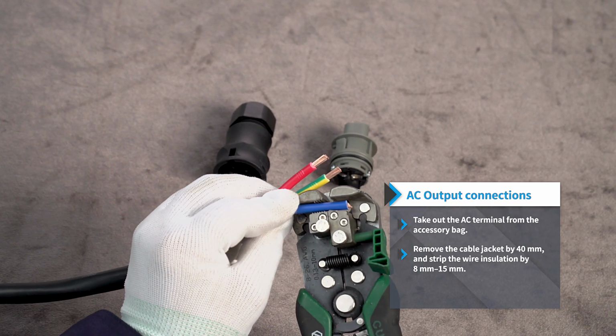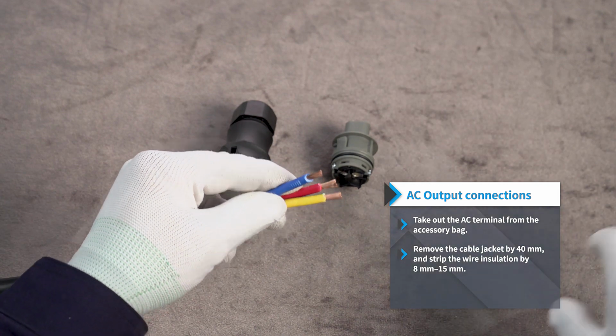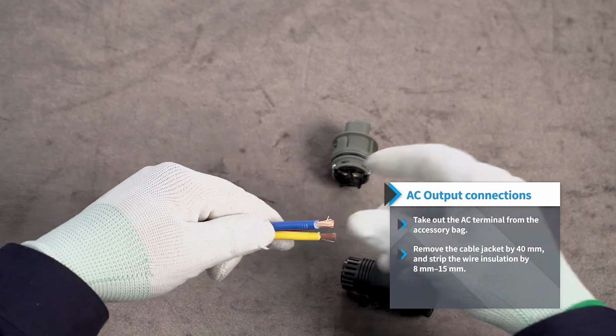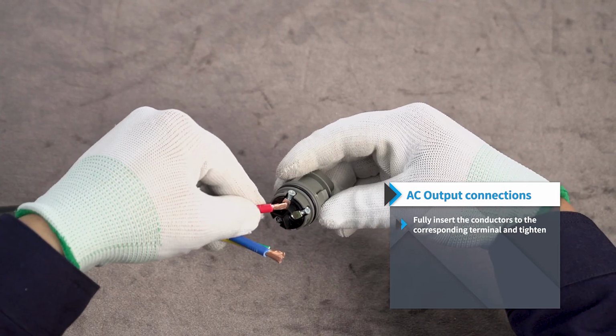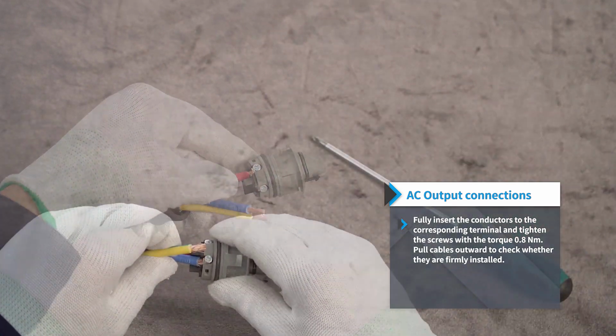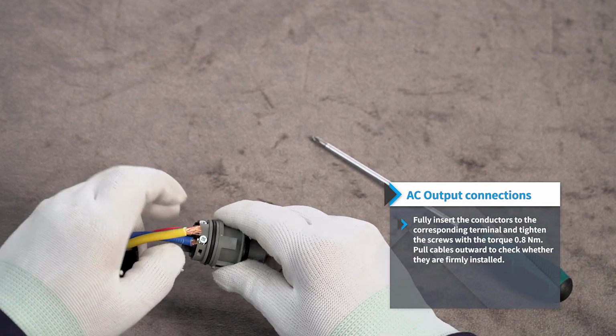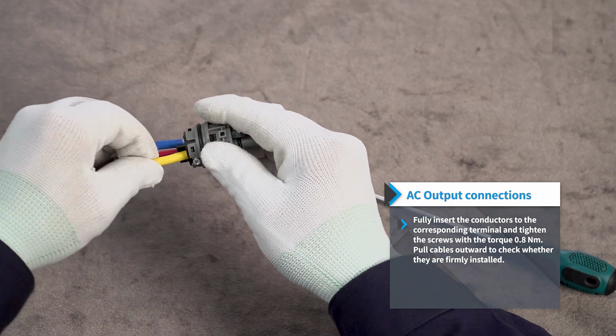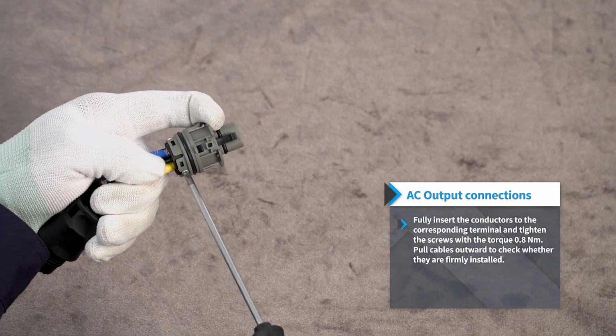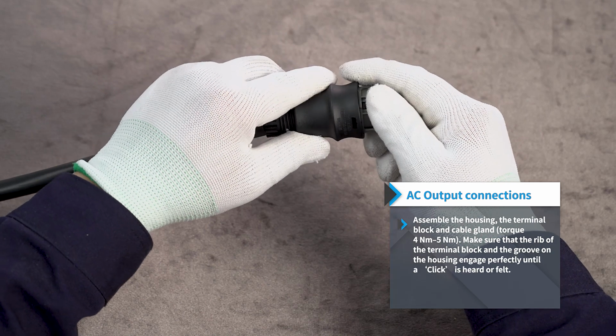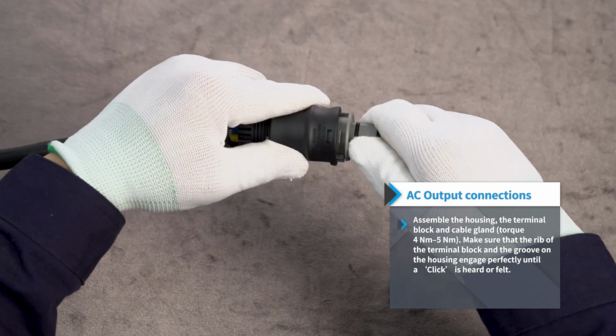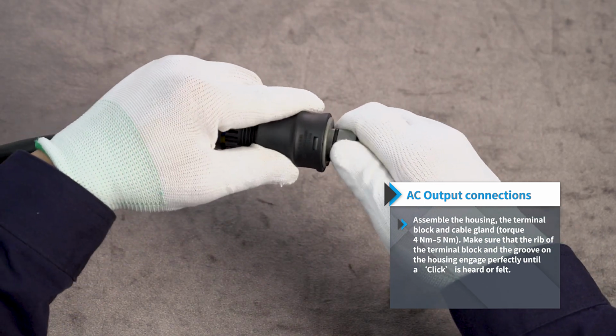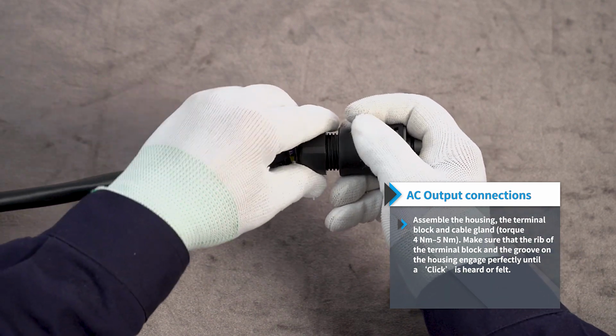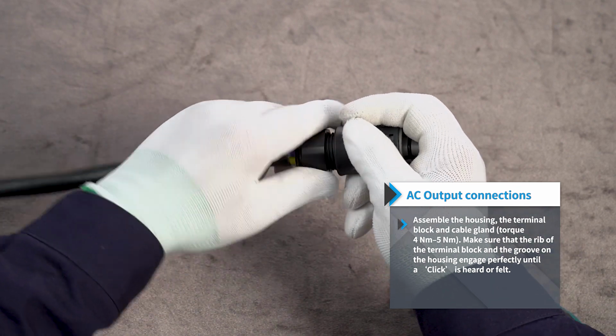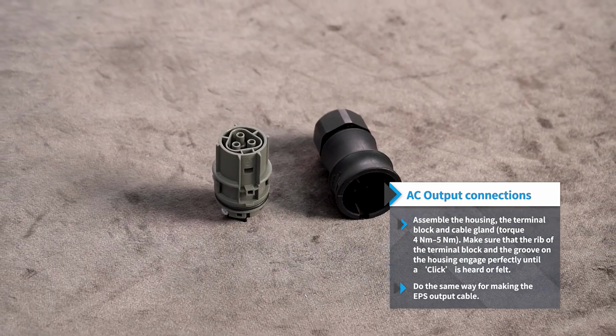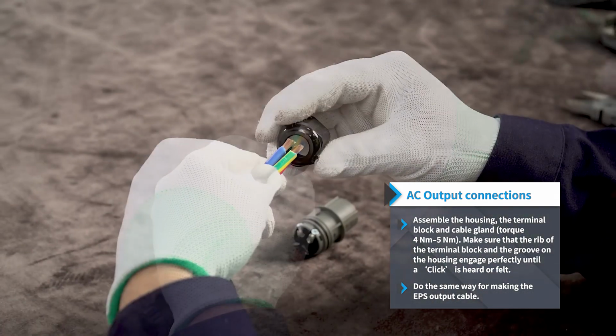And strip the wire insulation by 8 mm, 15 mm. Fully insert the conductors to the corresponding terminal and tighten the screws with the torque 0.8 Nm. Pull cables outward to check whether they are firmly installed. Assemble the housing, the terminal block and cable gland, torque 4 Nm–5 Nm. Make sure that the rib of the terminal block and the groove on the housing engage perfectly until a click is heard or felt. Do the same way for making the EPS output cable.